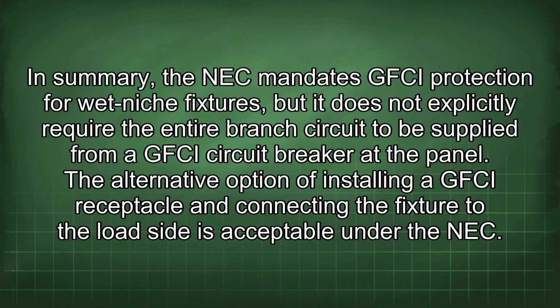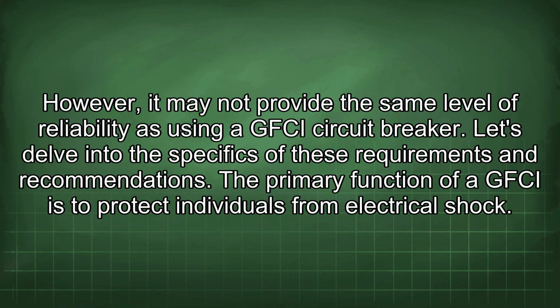In summary, the NEC mandates GFCI protection for wet niche fixtures, but it does not explicitly require the entire branch circuit to be supplied from a GFCI circuit breaker at the panel. The alternative option of installing a GFCI receptacle and connecting the fixture to the load side is acceptable under the NEC. However, it may not provide the same level of reliability as using a GFCI circuit breaker. Let's delve into the specifics of these requirements and recommendations.